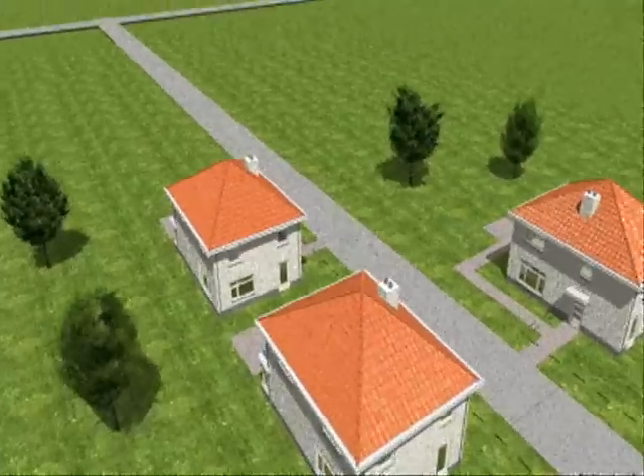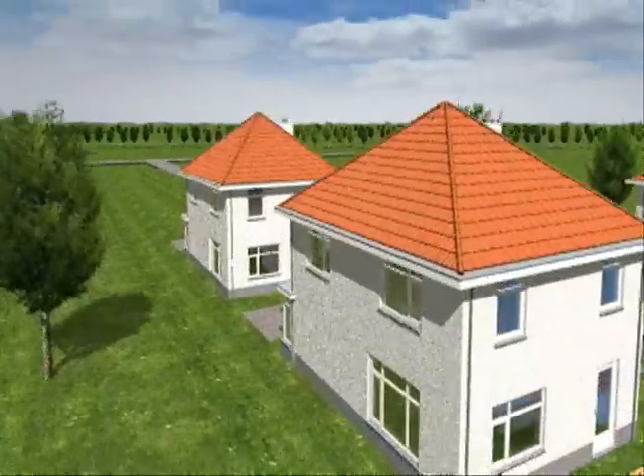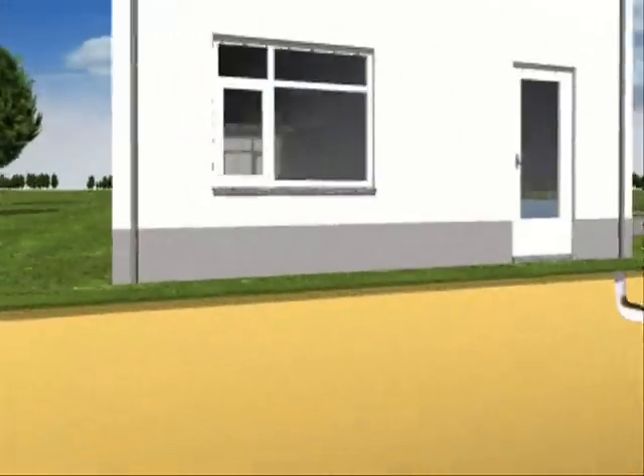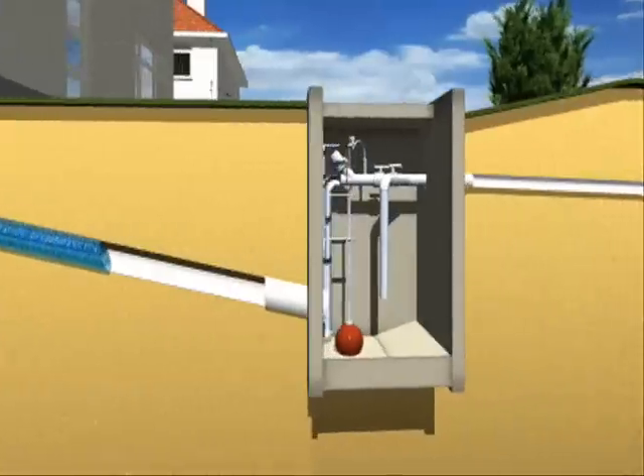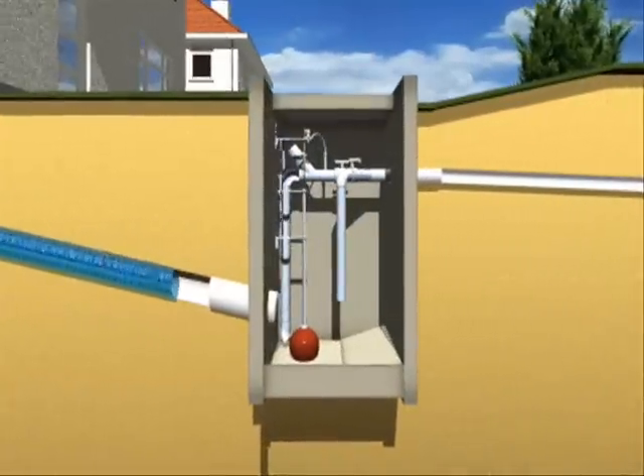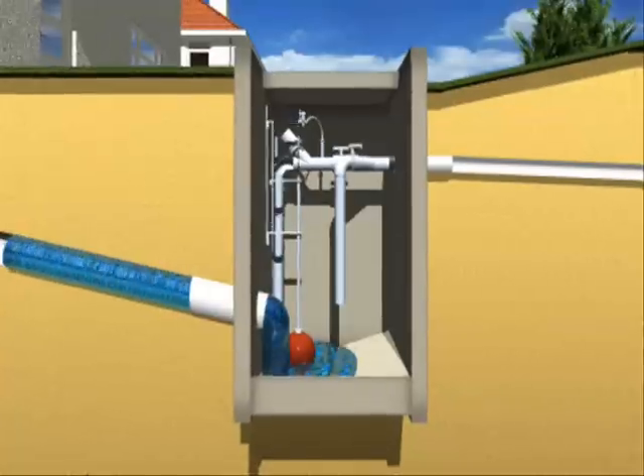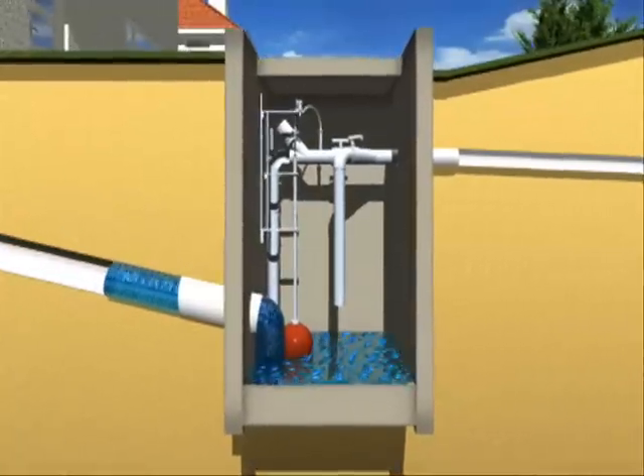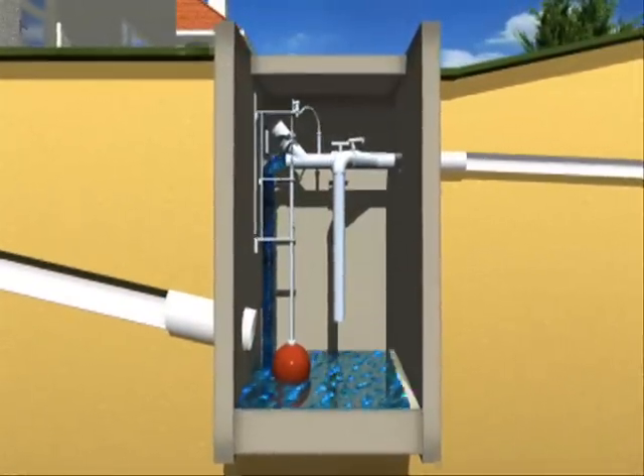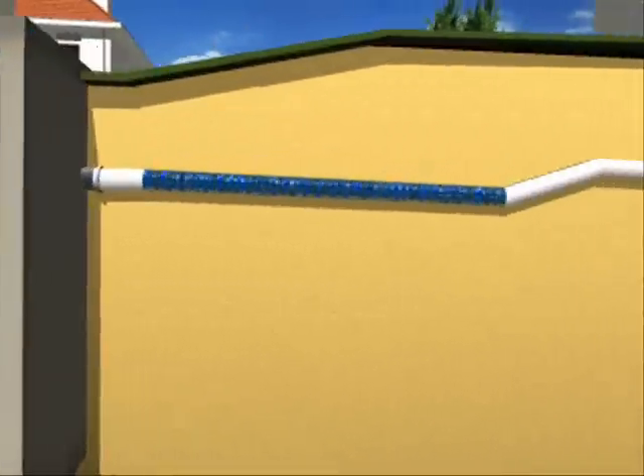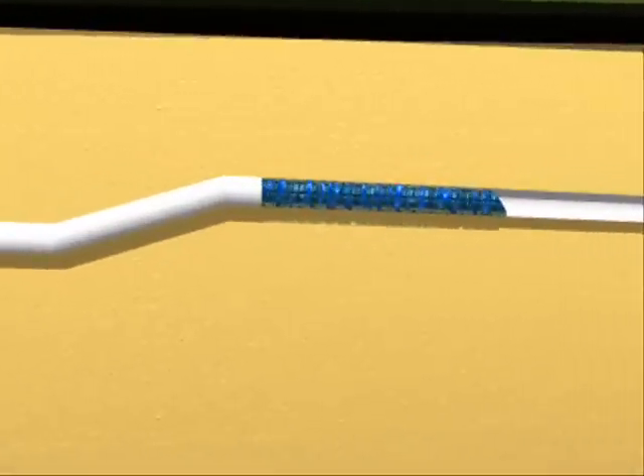Once the float switch is activated, an adjustable batch volume of some 25 to 125 litres of sewage is discharged into the vacuum main. Sewage and air are simultaneously and automatically removed from the chamber in only 5 to 15 seconds.